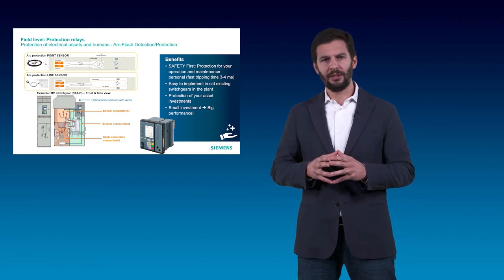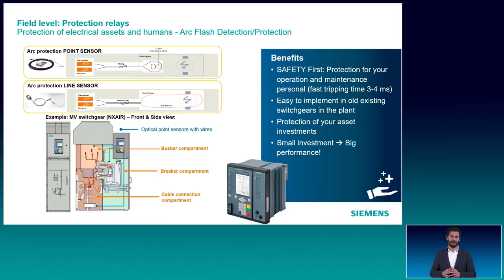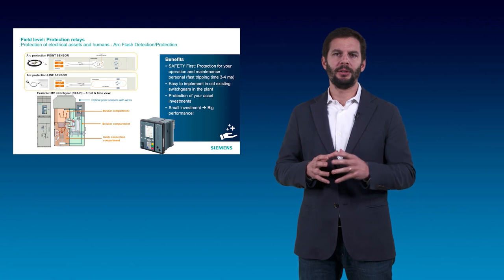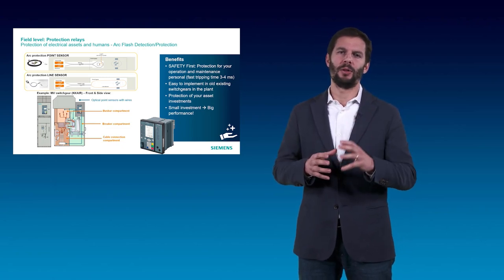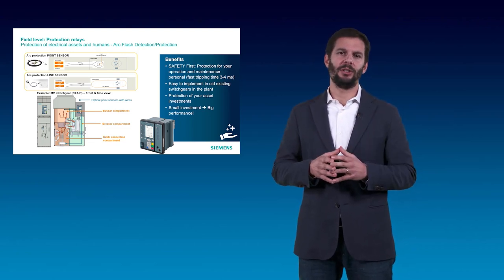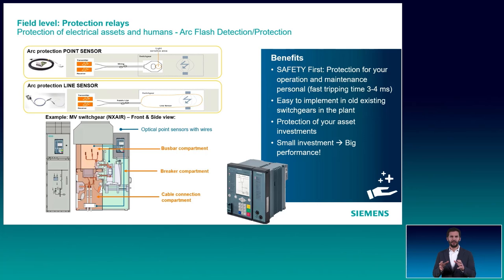Still on the topic of safety, if we look into an industrial plant, we will see a considerable number of medium-voltage switch gears. Having this primary equipment around also brings additional risks, first of all to the persons who have to operate them. In order to avoid that, we have arc flash detection. In one model of the protection relay, SIPROTEC 5, we can connect three point or line sensors, and in one device we can have up to five modules — meaning a total of 15 sensors can be connected, sensing the different switch gear compartments: the bus bar, breaker, or cable connection compartment. The protection itself is very fast, clearing a fault in three to four milliseconds.